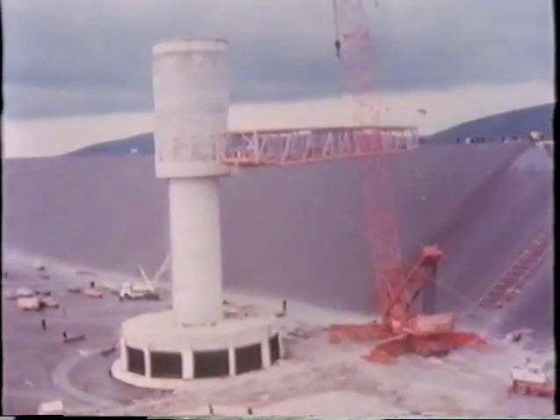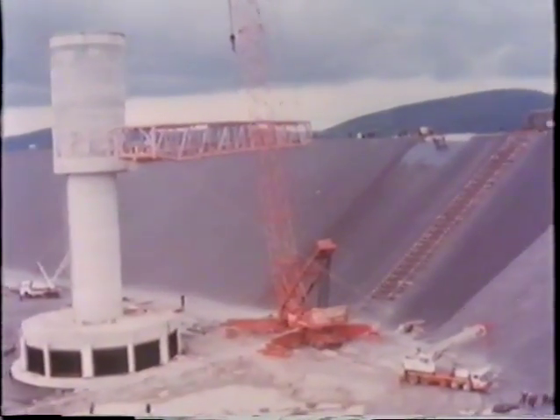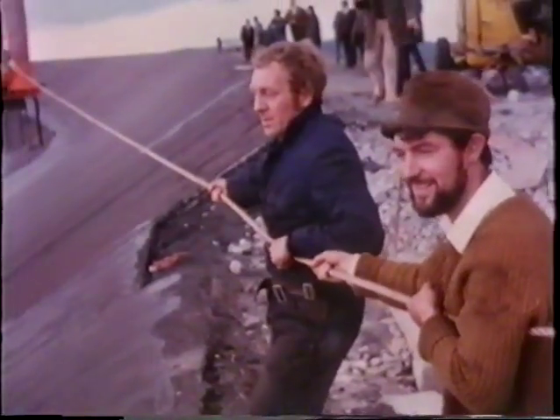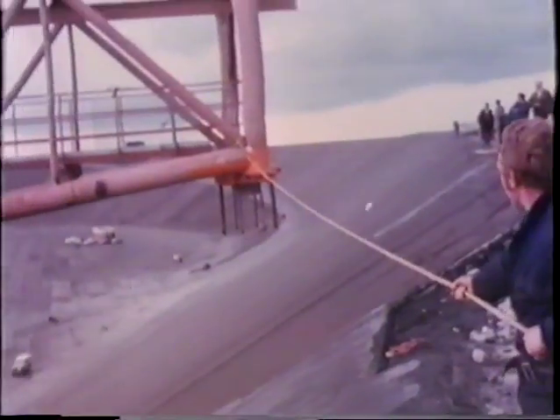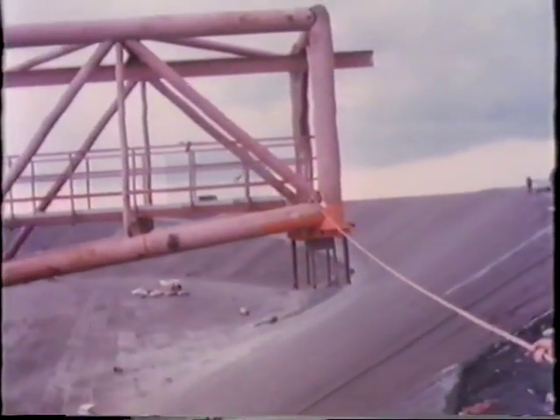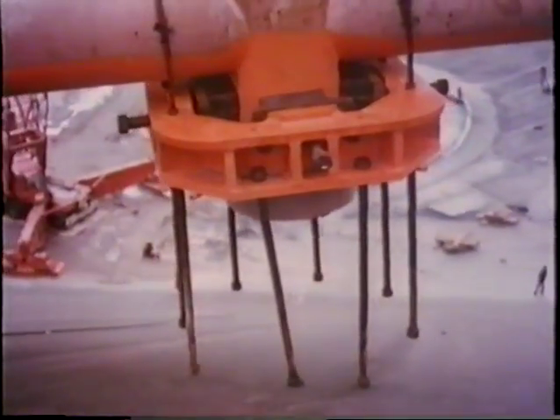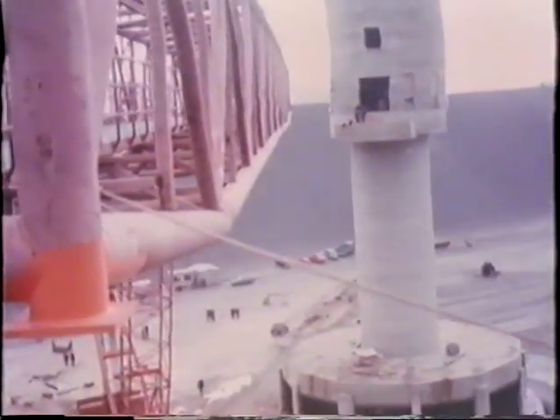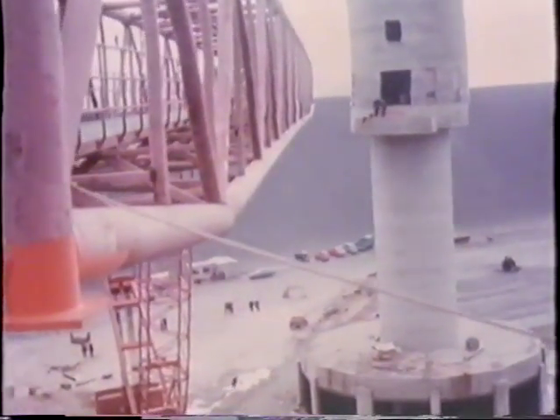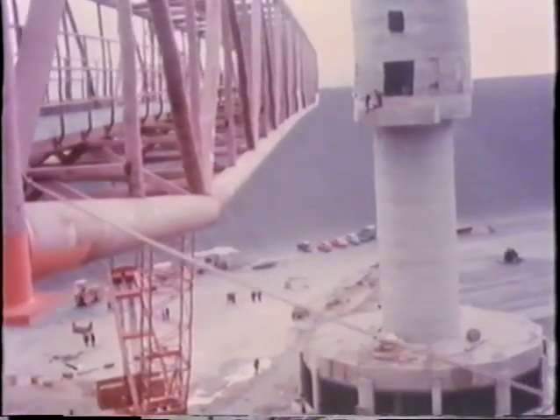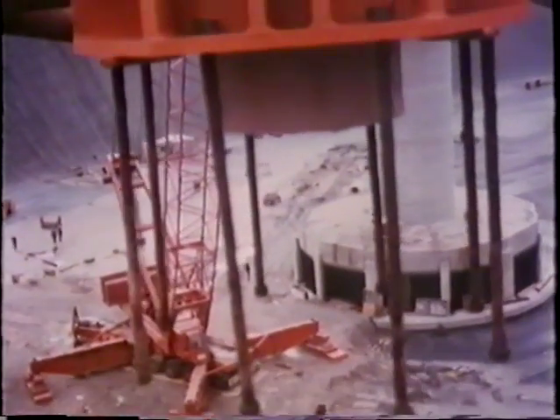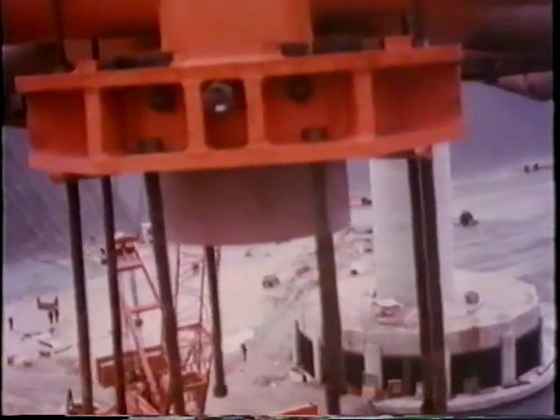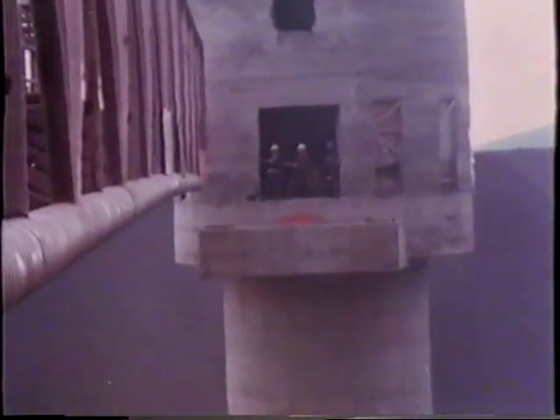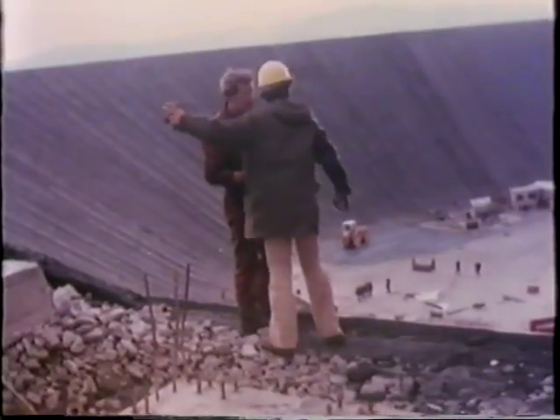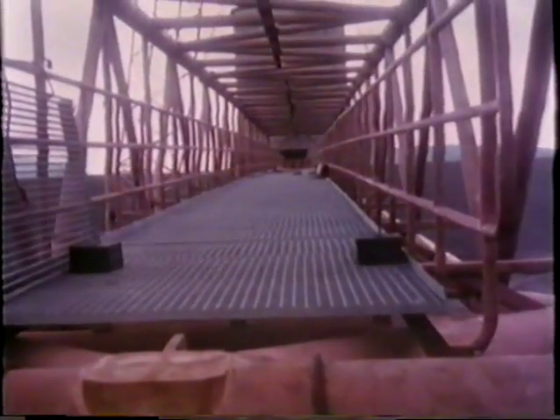Water is drawn from the upper reservoir into the pressure shaft and hence to the power station below through an intake structure of reinforced concrete. The tower above it is provided with access from the embankment by means of a tubular steel bridge designed for stability in high wind conditions. The finished tower is 39 meters high with an overall weight of some 5,000 tons and a safety factor of 1.4 against uplift when the interior is empty of water.